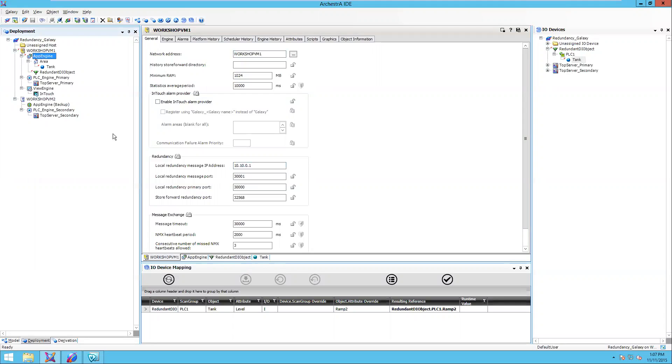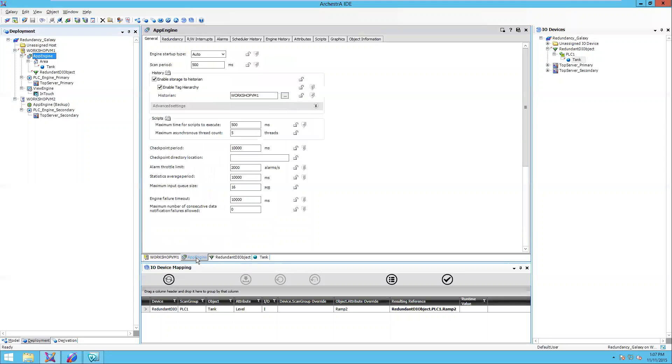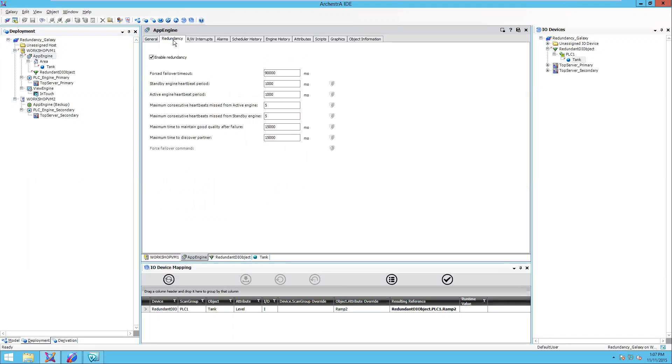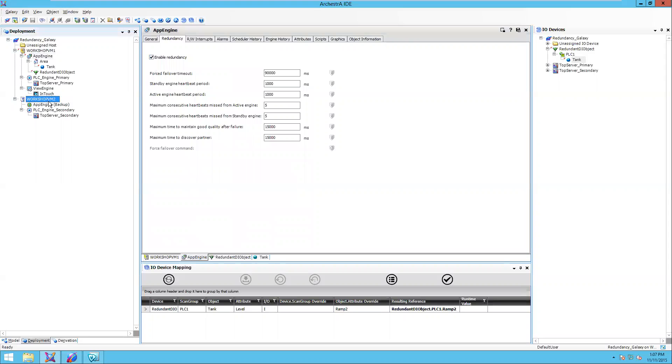Next, I have an engine. The engine is configured to store and forward the data to the Wonderware historian. I've put my historian computer name here, which in this case the historian is running locally on Workshop VM1. The engine has also been enabled for redundancy. I've checked the box to enable redundancy. When I did that, it creates a backup engine, which I placed on my Workshop VM2 computer.